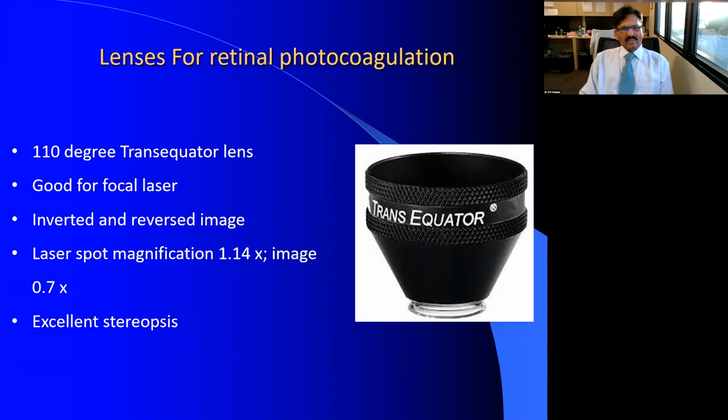Good for focal laser, inverted and reversed image. So you have to make sure you're not shooting the macula. Laser spot magnification is 1.14 and the image size is 0.7. It has an excellent stereopsis.